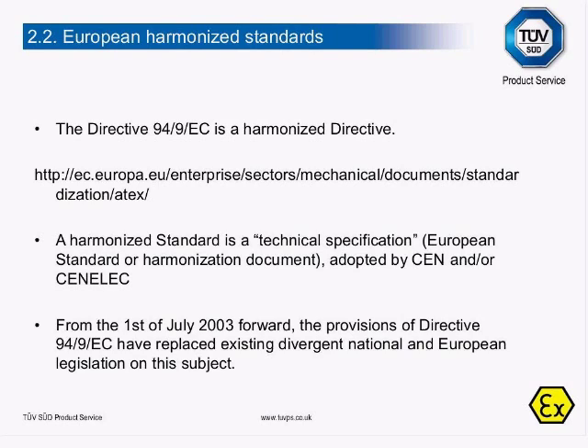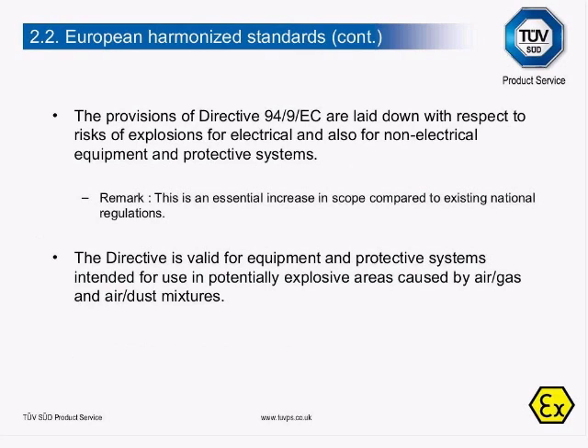Directive 94/9/EC is a harmonised directive. A harmonised standard is a technical specification — a European standard or harmonised document adopted by CEN and/or CENELEC. From 1 July 2003 onwards, the provisions of Directive 94/9/EC replaced existing divergent national and European legislation on this subject. The provisions are laid down with respect to the risks of explosions for both electrical and non-electrical equipment and protective systems. The Directive is valid for equipment and protective systems intended for use in potentially explosive areas caused by air-gas and air-dust mixtures.